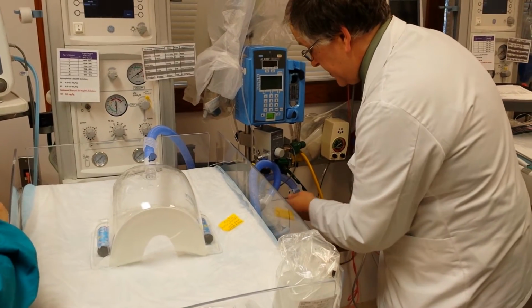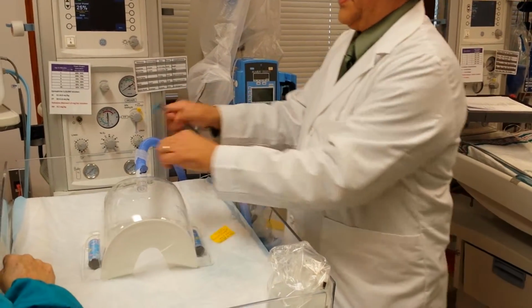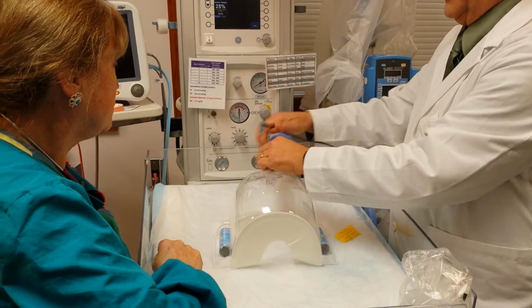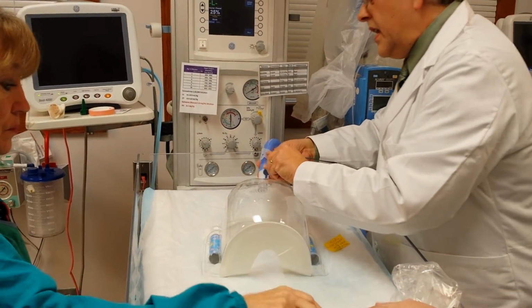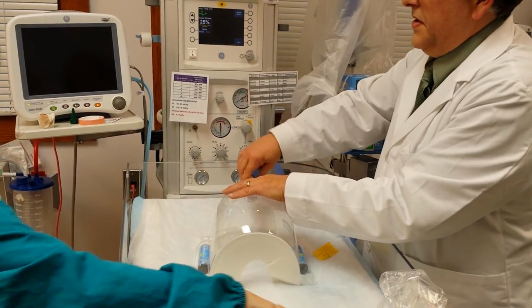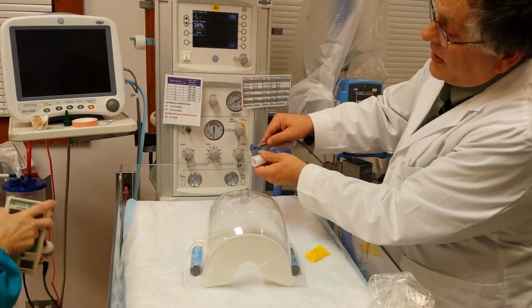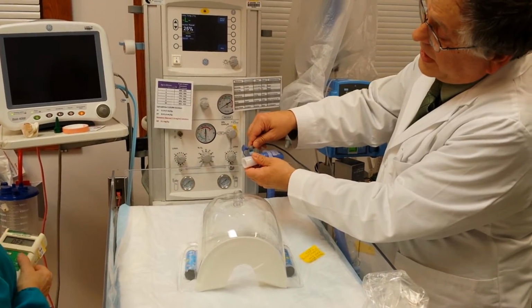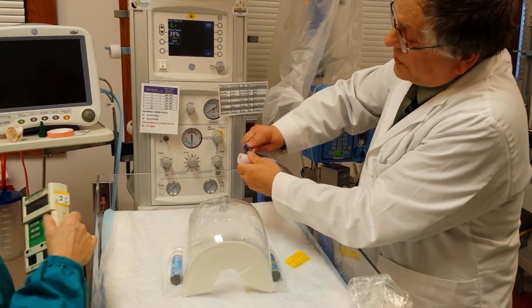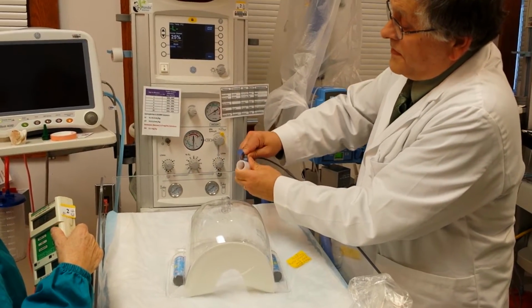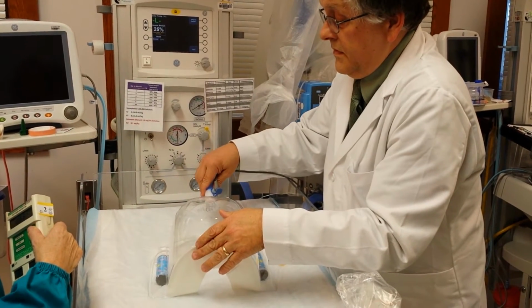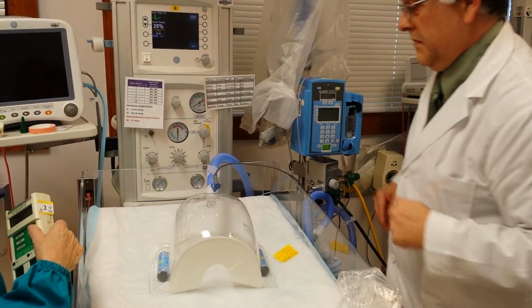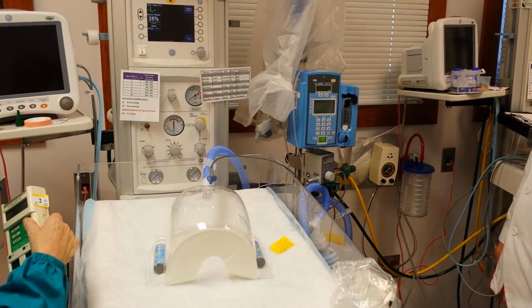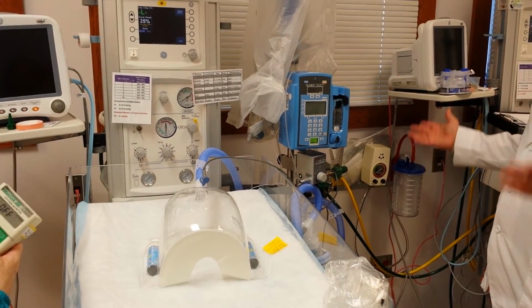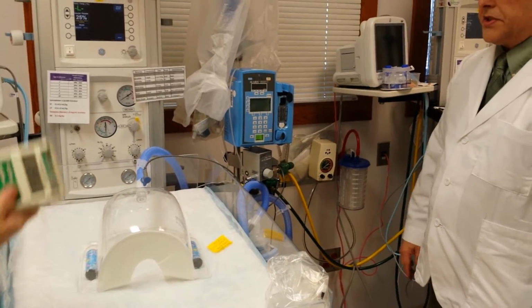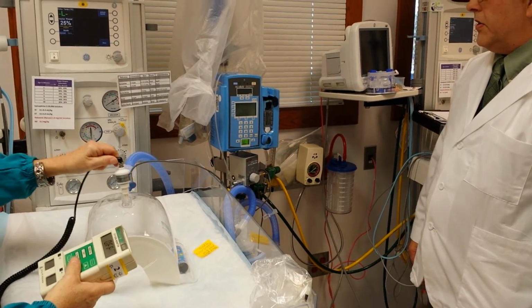Now, what else do we need to hook up? There's an open temp probe hole. The temp probe is right here. And you just twist this. It's actually easier when it's not on the hood. You twist this as far as it'll go. Twist and push until the blue disappears. Okay. And now the flow is going. It's getting the oxygen. We just need to turn the heater and the humidifier on.